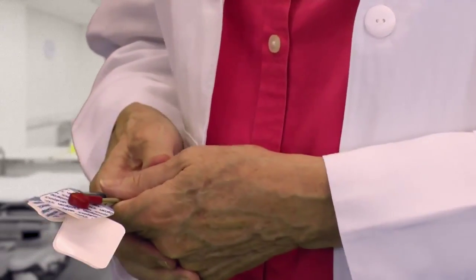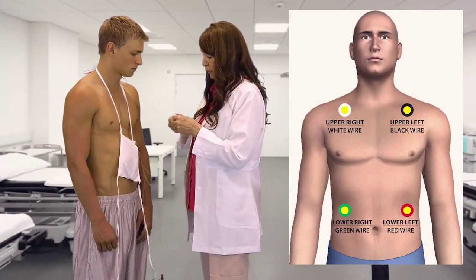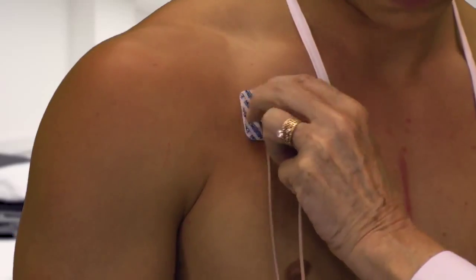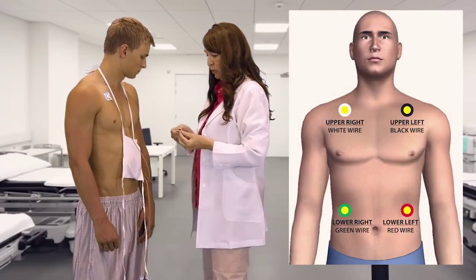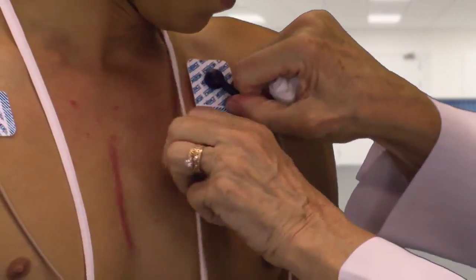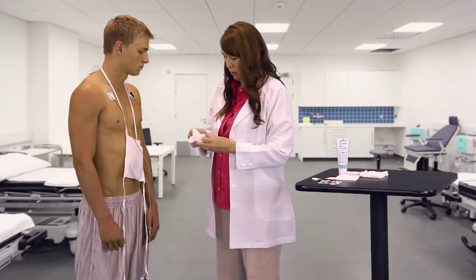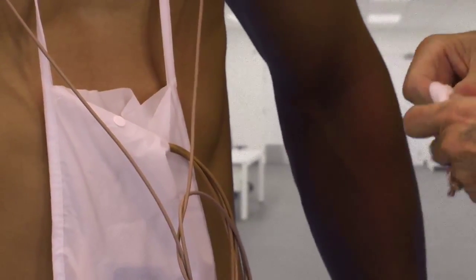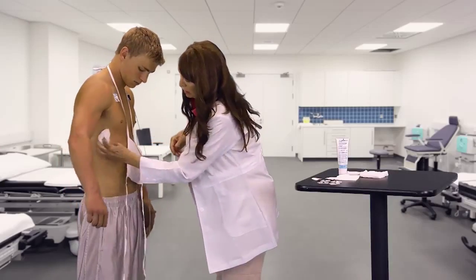Then on the top of these wires, I'm going to take the black and the white — RA, right arm. I'm going to take that seal off and put it right where you washed. Push on it just a little bit so we have better contact. This one is LA for our left arm, or what we consider the left arm. Turn it over and wipe it off.